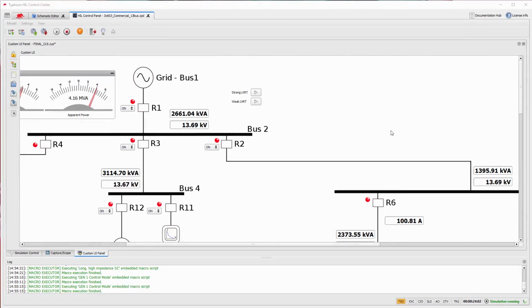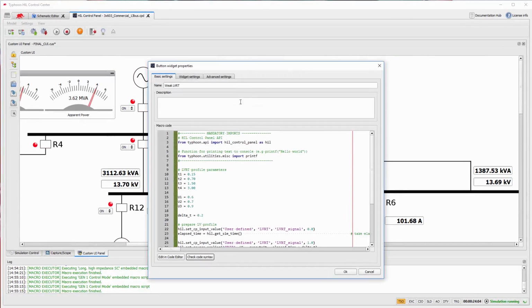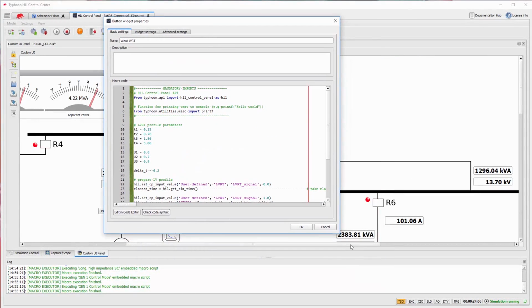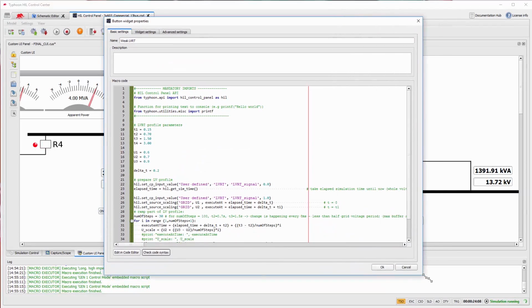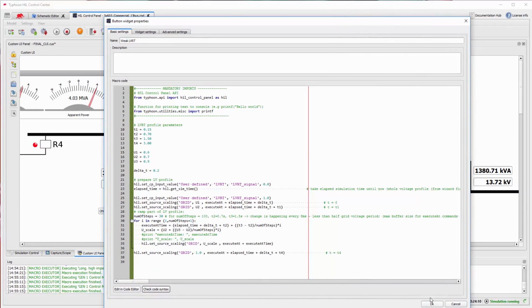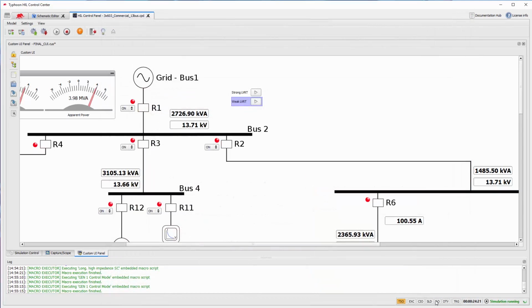In the second scenario, we implemented two low voltage ride-through tests by writing scripts inside the button widget. There are two types of LVRT implemented, a weak and a strong. The strong one is exactly the same curve as described in the BDEW guidelines, while the weak follows the same pattern but with smaller voltage dip levels.